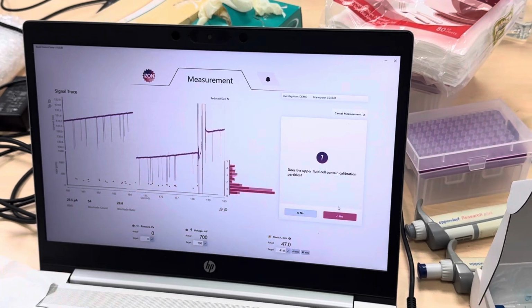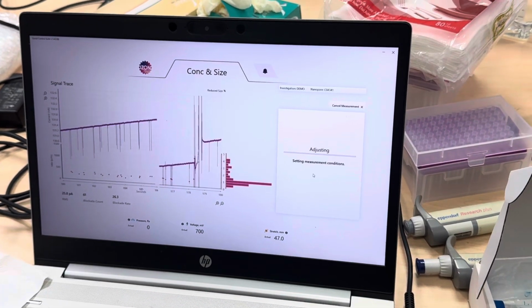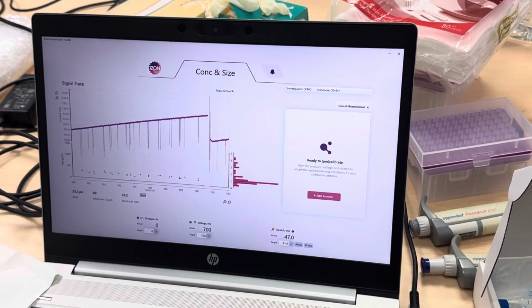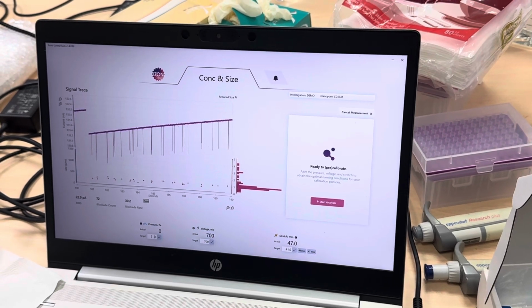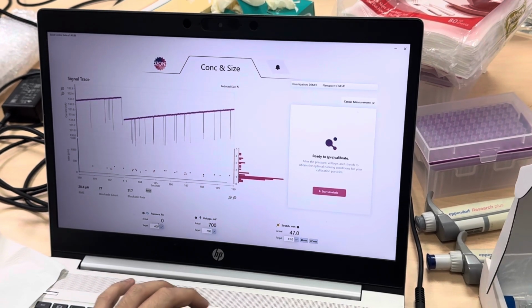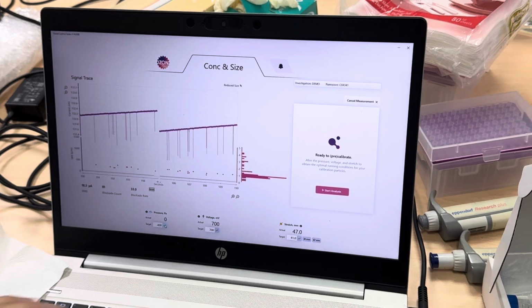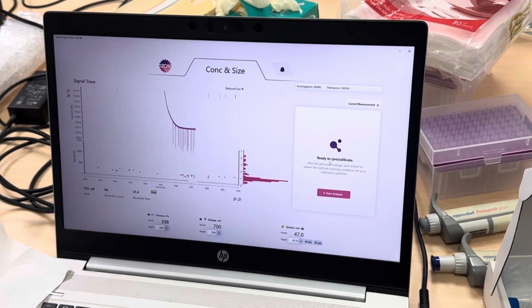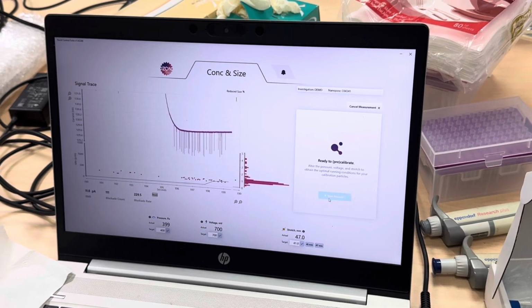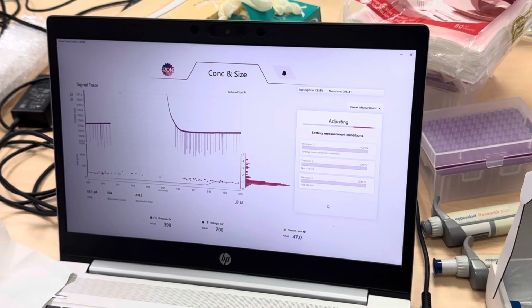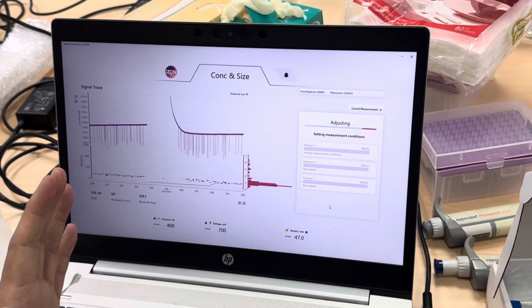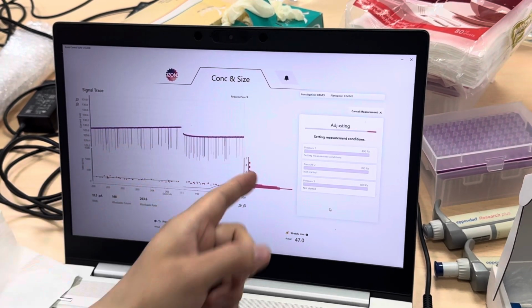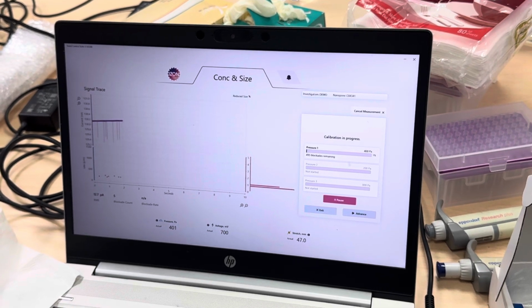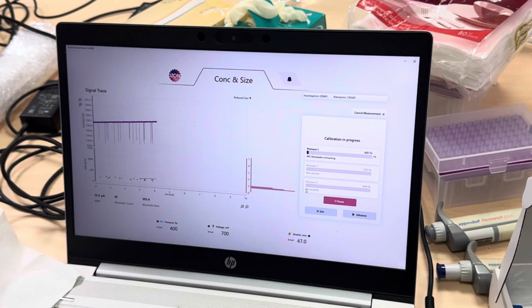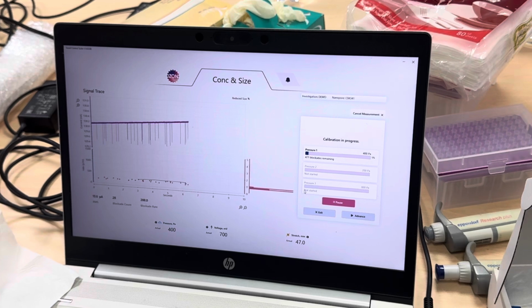It's guided mode. So yeah, it contains the particles. And then we will set middle pressure. So it's around 400. Usually we use 400. And then we click Start Analyze. So the system is recording the calibration particle data. Yeah. So it's under 3 different pressures. This procedure is automatic, so you just sit and wait there.